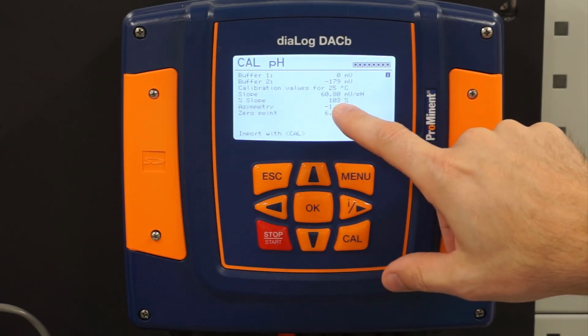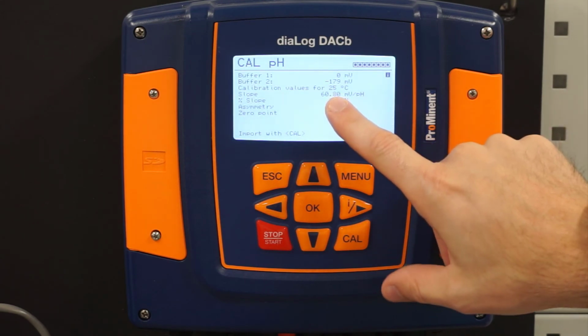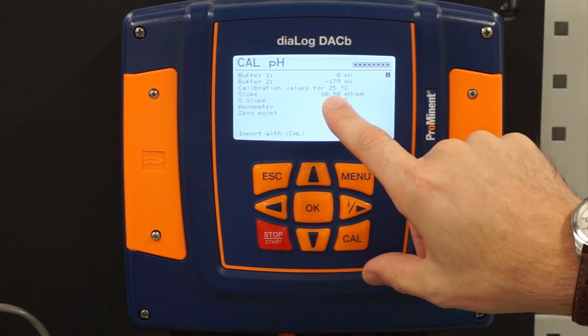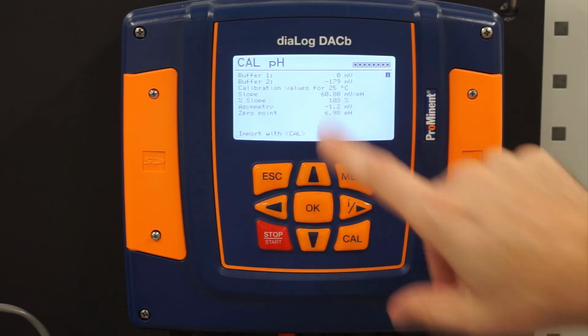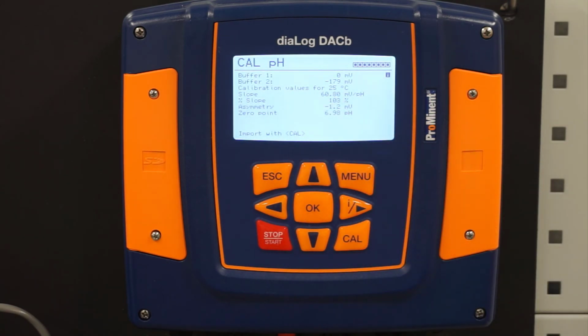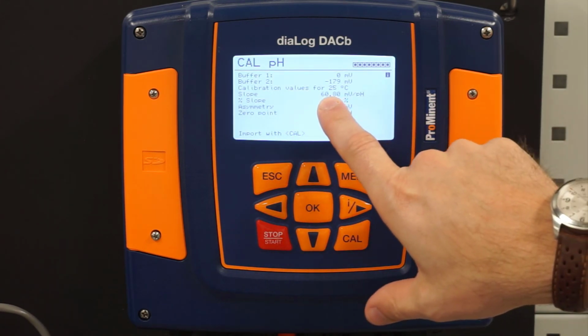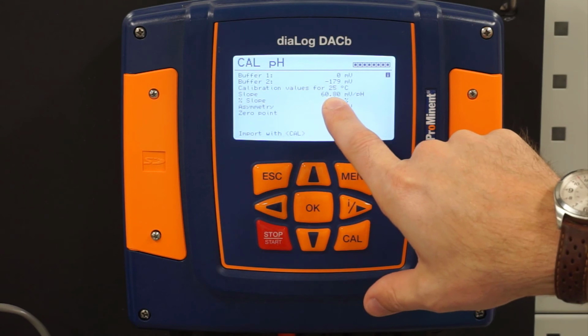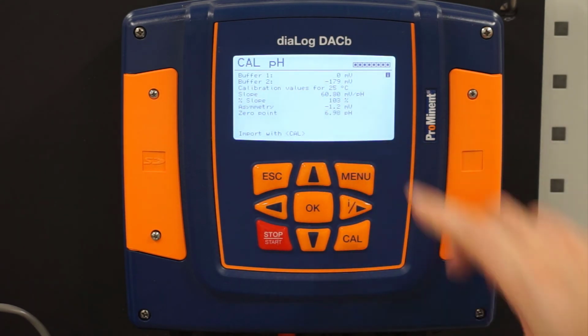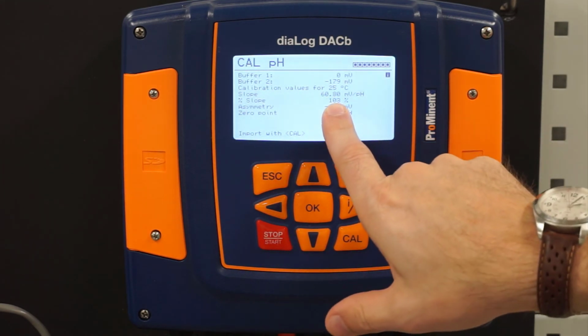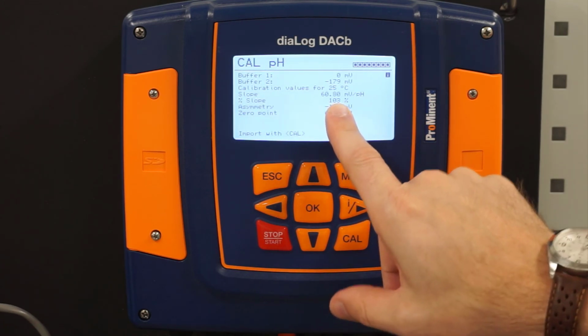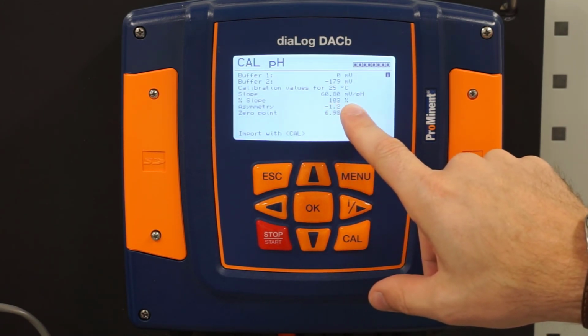So we use the simulator, so it's a little bit better than what you would expect to see. A perfect millivolt signal from a pH sensor would be 59.17 or 18 millivolts. That would be perfect. You're not going to see much better than that. But because we are using a simulator, we would not expect to see 60.8 on an actual pH sensor. So 100% would be near that 59.18 or 17 millivolts per pH.